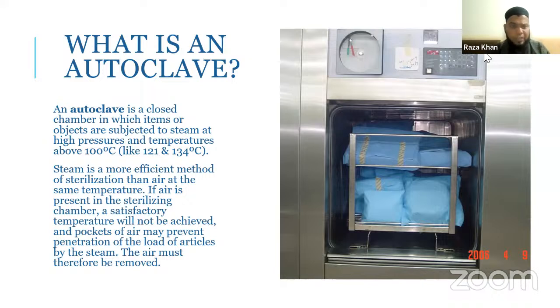As we discussed, this is a very efficient and good method of sterilizing items. In the vacuum method, all the air is removed from the start of the cycle so that heat penetrates well in the chamber, because air pockets usually prevent the penetration or the equalizing of heat. So the vacuum method is very effective.